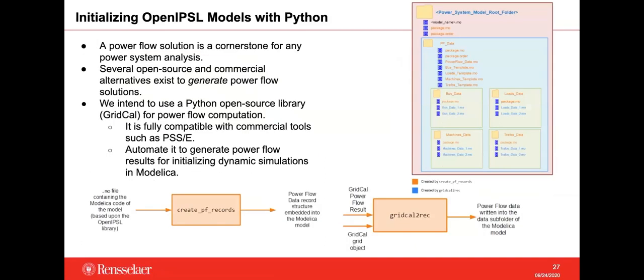We are also working on initializing OpenIPSL models using powerflow results from a Python application called GridCal. A Python script takes the .mo file and converts it into a GridCal-readable document, which GridCal then reads to perform the powerflow. The powerflow results are used to populate records located in a sub-package of the model, allowing the model to initialize its simulation at a specific equilibrium point.